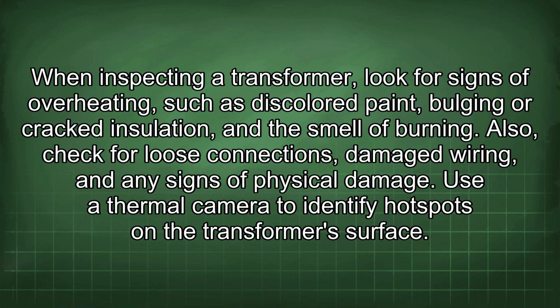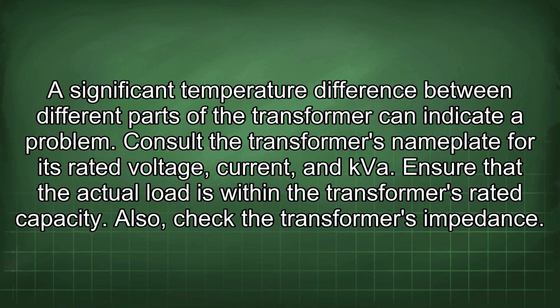When inspecting a transformer, look for signs of overheating, such as discolored paint, bulging, or cracked insulation, and the smell of burning. Also, check for loose connections, damaged wiring, and any signs of physical damage. Use a thermal camera to identify hotspots on the transformer's surface. A significant temperature difference between different parts of the transformer can indicate a problem.